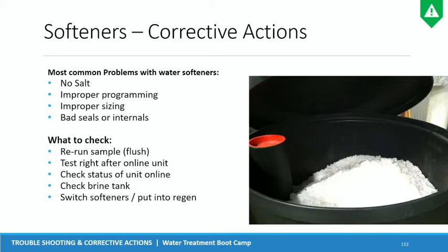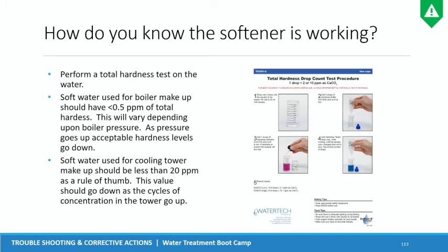How do you know the softener is working? Run a hardness test, right? This is one of the tests that we're gonna have you run in your facility. If you have softeners, you should be testing and making sure that your softeners are working. Whether it's feeding directly into your cooling tower or into your boiler, or if it's feeding into an RO, you should probably be checking the softeners feeding into the RO, because you don't wanna shorten the lifespan of those RO membranes.